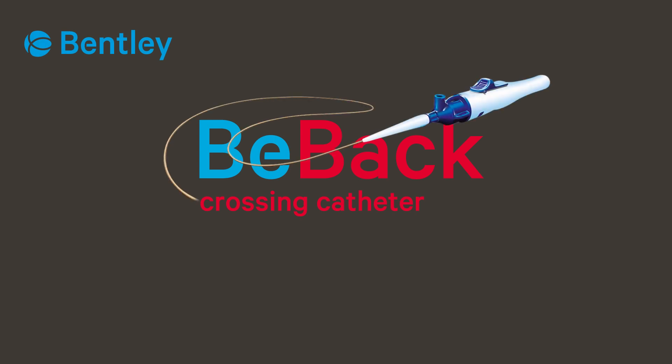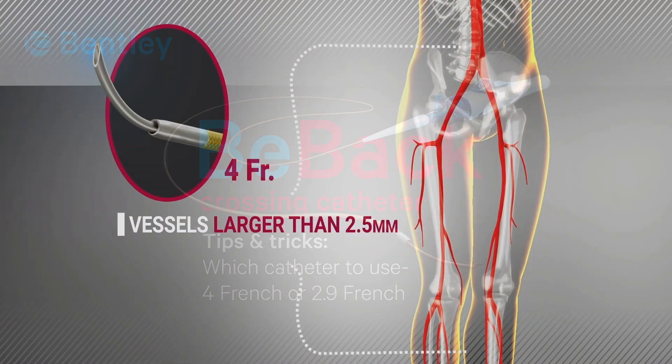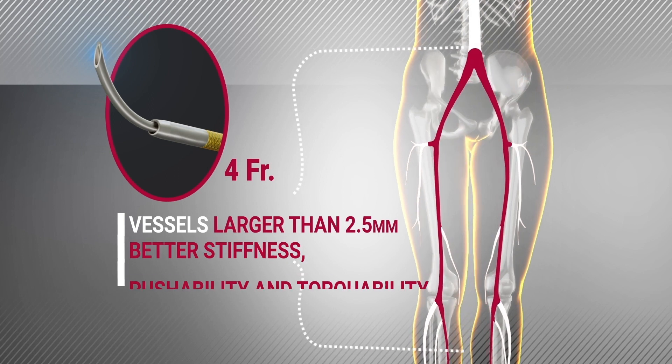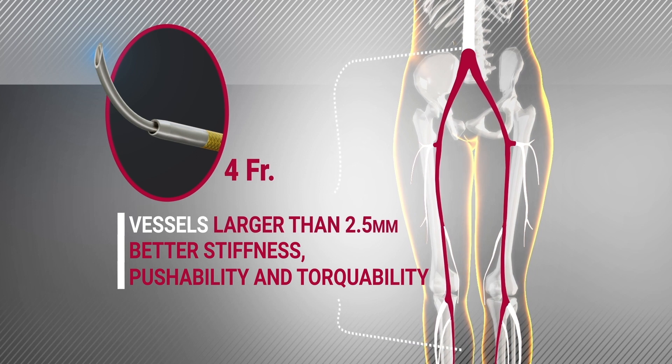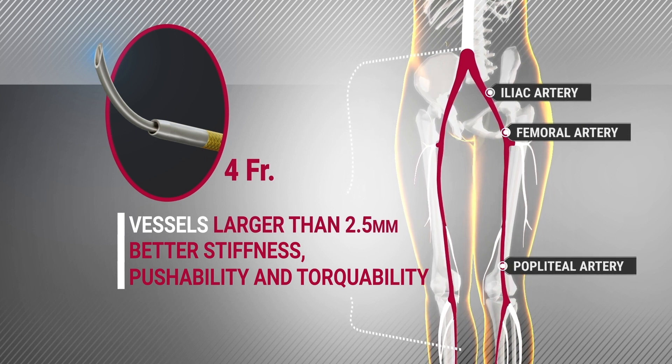Here is a guide to selecting the optimal BeBack catheter for your case. The 4 French catheter is stiffer and has greater pushability and torqueability. We therefore recommend the use of the 4 French device wherever possible. This applies for all above-the-knee cases, so long as the vessel diameter is greater than 2.5 mm.